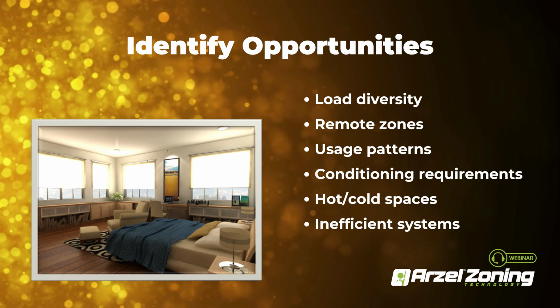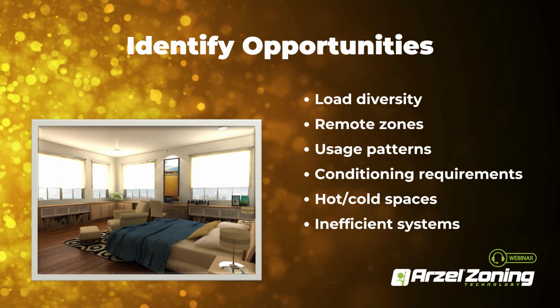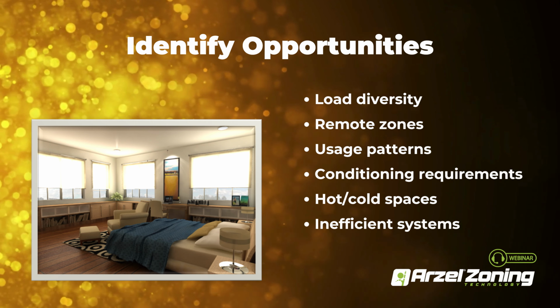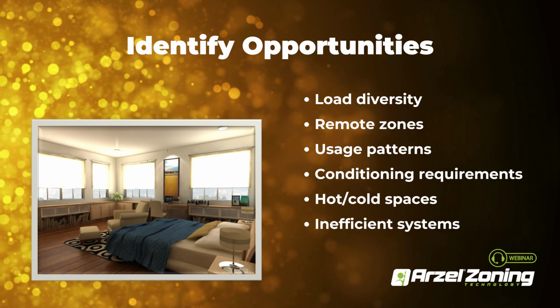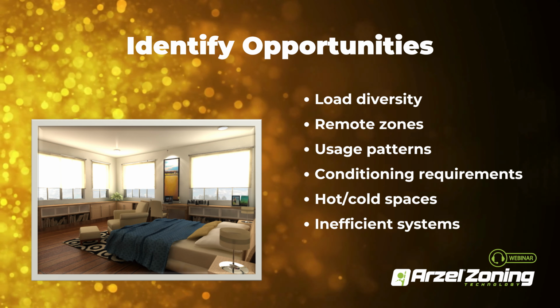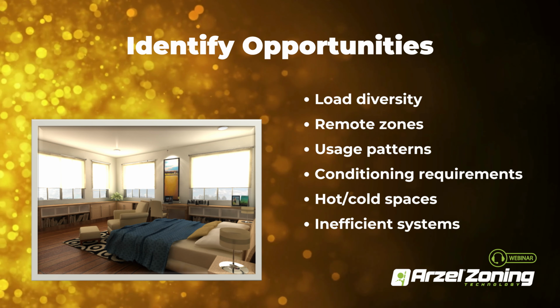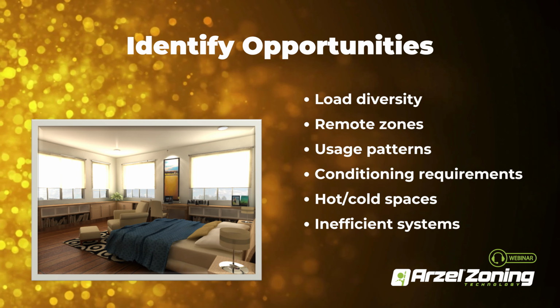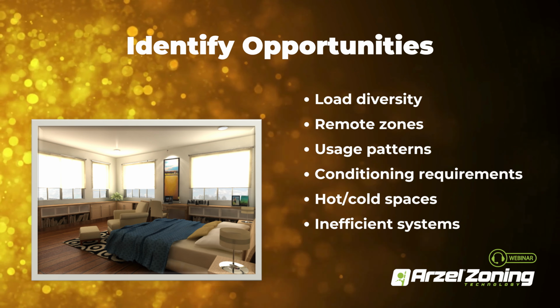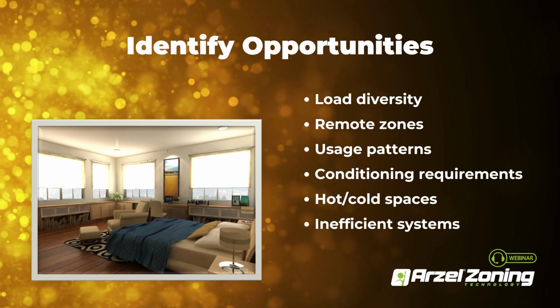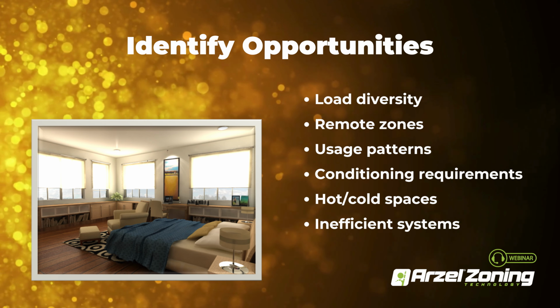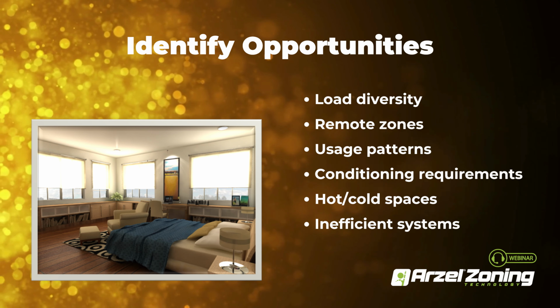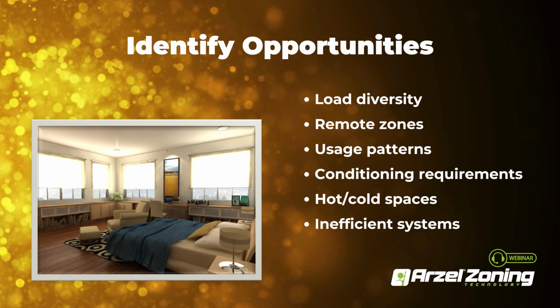Then there are inefficiencies in the system. A lot of times ductwork isn't really designed to distribute the airflow properly anymore, so a little extra control to direct that air where it needs to be goes a long way toward improving an efficient system. That said, the ductwork capabilities still have to be there. If we don't have the ductwork to serve a zone, zoning's not going to fix that. But if the ductwork's there, zoning can optimize it.